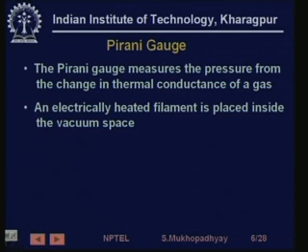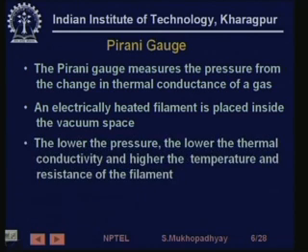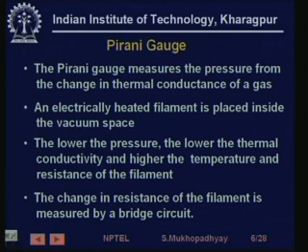Therefore, an electrically heated filament is placed inside a vacuum space. Vacuum space means a very low pressure space. The lower the pressure, the lower the thermal conductivity of the medium and the higher the temperature and the resistance, because less heat is being taken away. So the temperature of the filament will increase, and therefore its resistance will increase. If we put that filament into a circuit, we can directly sense the resistance change. So it is measured by a bridge circuit.